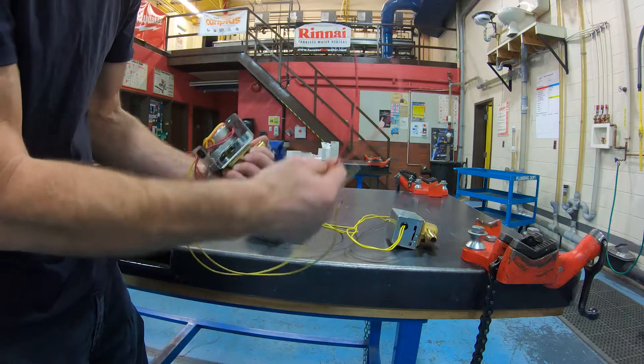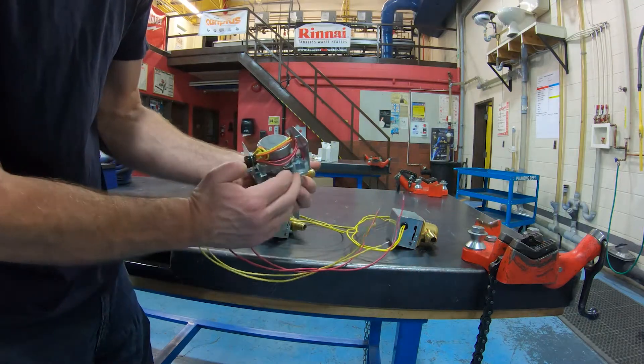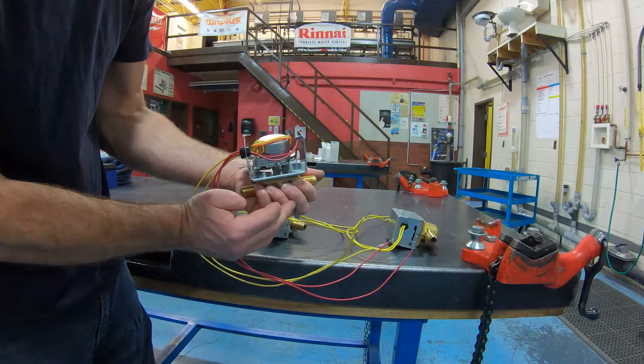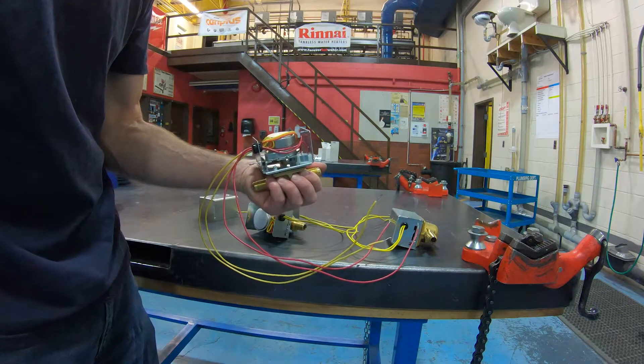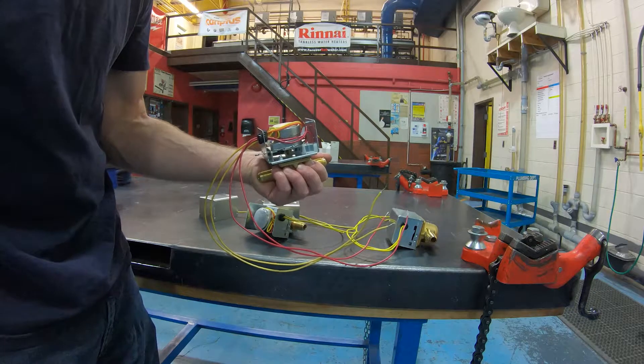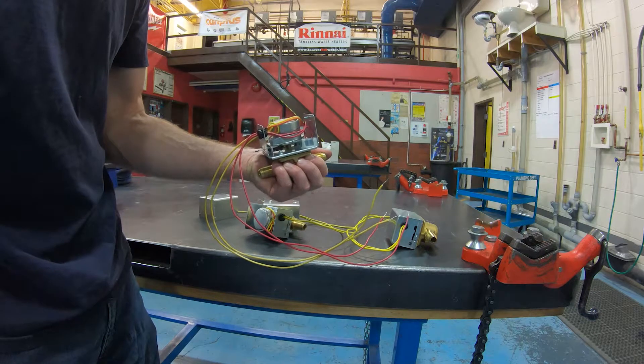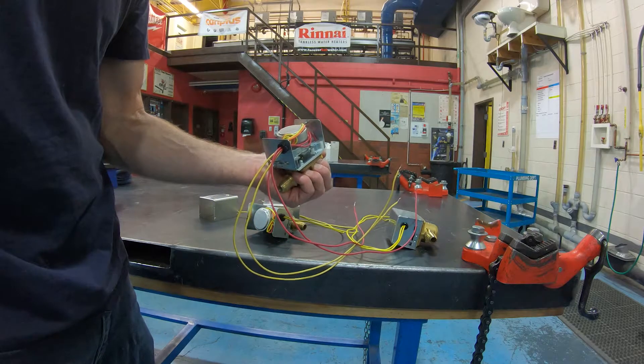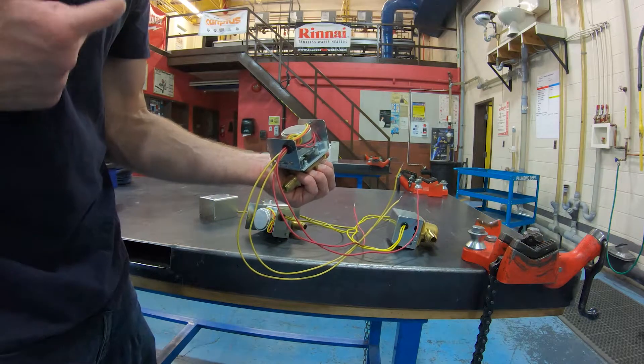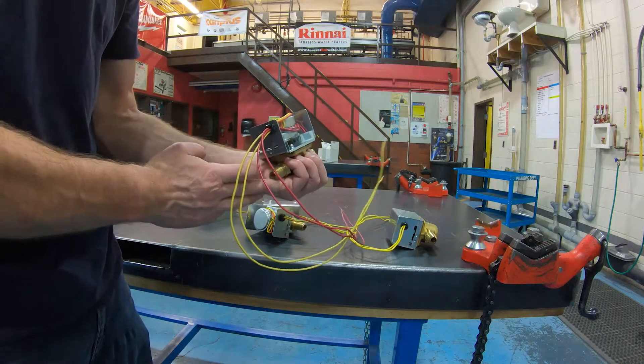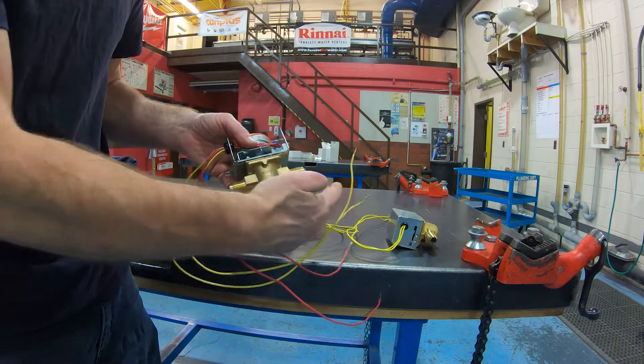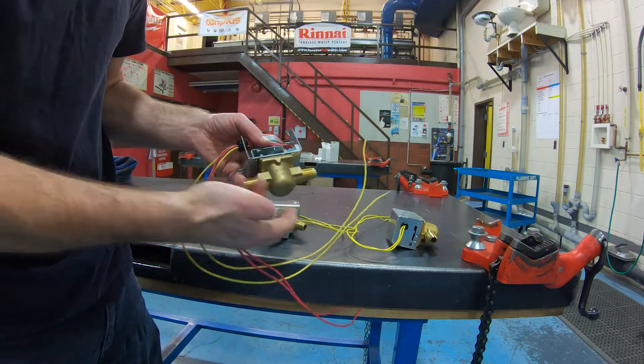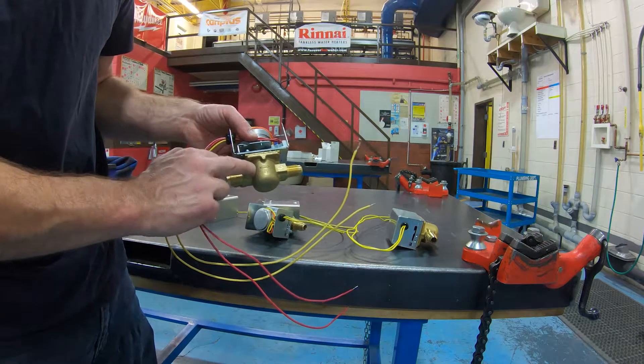However, the two red wires go to an end switch, which doesn't look like much, that's that thing right there, but that is a little switch that will close or allow power to go through it just like a regular light switch when the zone valve is all the way open. So once again, this is normally closed. That means that you need to put power to it, 24 volts for this one to open it up and allow water to flow through it. And both of these have an inlet and outlet port. We can actually see a directional arrow there.